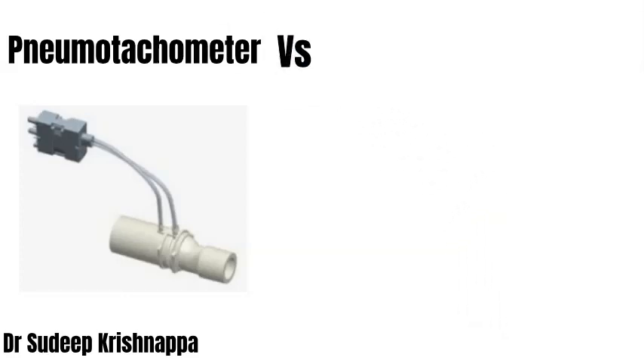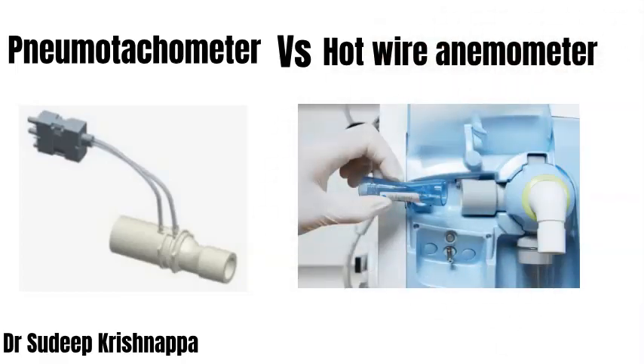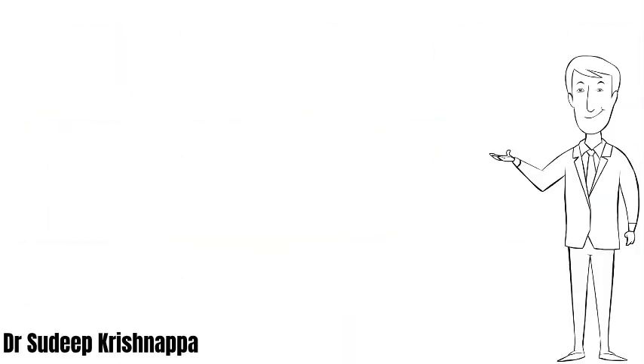Because the Drager machines use a hot wire anemometer, certain precautions have to be taken in some of the older Drager workstations like Drager Fabius or Fabius Plus when desflurane is being used. The picture in the next slide is a side-on view of the hot wire anemometer flow measuring device used in the Drager anesthesia machines. This device is interposed along the path of the gas flow.